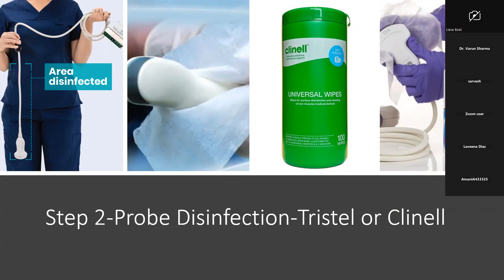Just be careful. It has one wipe, which is a saline wipe, which cleans grit and dirt off the probe. So if this has got blood stains or stuff on it, it will give you a really good clean. It then has a disinfecting wipe, which needs activation. So you have a wipe that's separate to this Tristel foam. And once it activates, you get this very strong pungent odor. So you clean the entire probe with it, and once it's dried, you have a third wipe which cleans off the disinfecting agent so that agent doesn't come into contact with the baby's skin. Really good stuff, but not cheap.